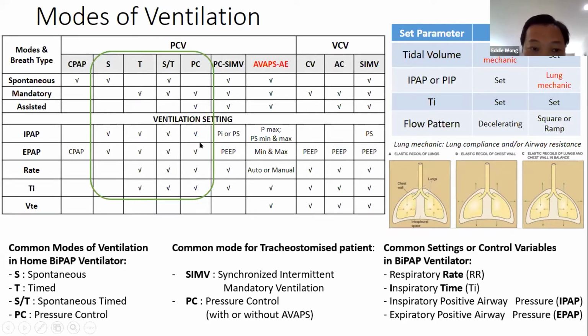So that's why if you notice, when it comes to ventilation settings under each mode, there's no setting called exhalation time. There's only a setting called rate and I time. Okay, besides the pressure settings, IPAP and EPAP, there's only rate and I time. So basically, of these 4 modes, you only need to learn 4 settings if you are using ST mode or pressure control mode at home. T mode is hardly used by any patient under ALS, unless the patient has a spinal cord injury at C3 or C4 cervical, because the patient cannot breathe on his or her own because of the spinal cord injury. Then normally this group of patients will use the T mode. So just forget about T mode here.